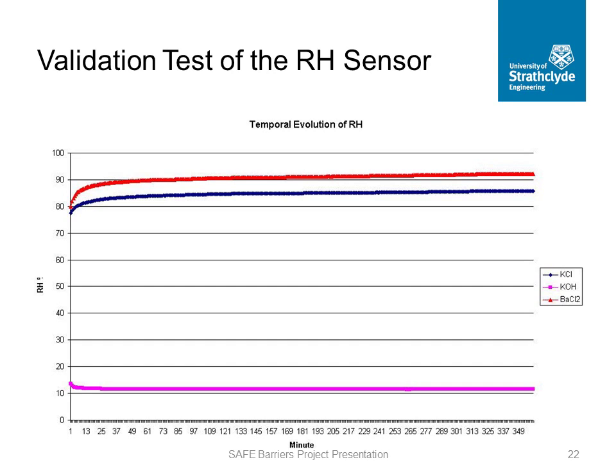This figure shows the short-term evolution of the relative humidity levels above three saturated solutions. After closing the container, the equilibrium of relative humidity is achieved in around 2 hours. We can also observe that in high relative humidity environments, there is a slow deviation of measured relative humidity above the theoretical value as time goes by. This offset of 3% approximately is coherent with the observations by the supplier of the sensor.